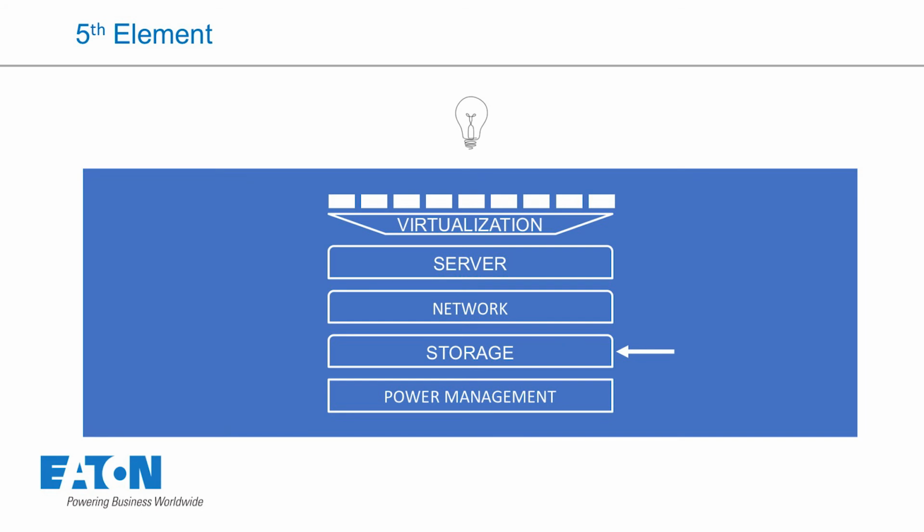Well, there's something called power capping. Most of you have heard of this term in the market, where we're trying to manage the power by simply either putting in standby or shutting off non-critical loads. And these are maybe equipment inside the rack that are consuming too much power that we don't really need in case of a disaster. Maybe servers or clients that are not active, and we have a storage device whose data isn't accessed frequently. So that could be part of the power capping situation.